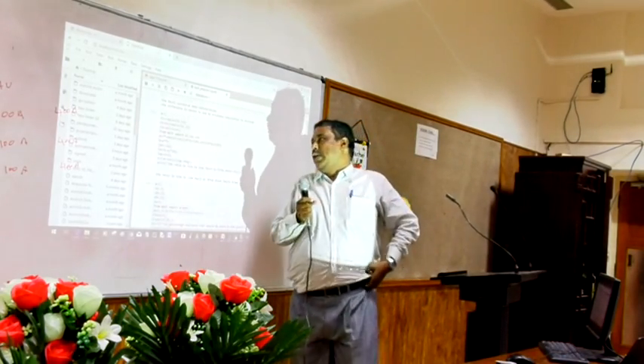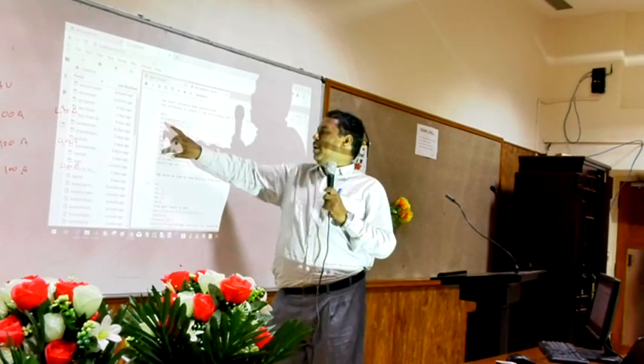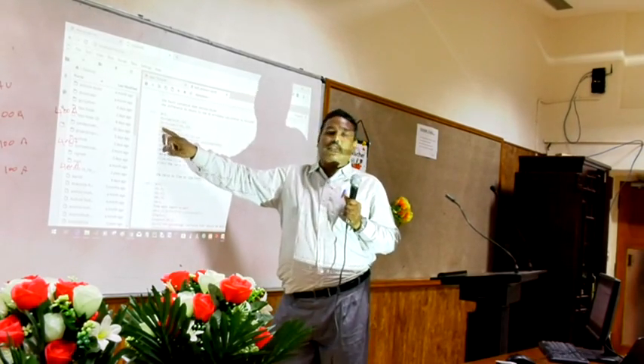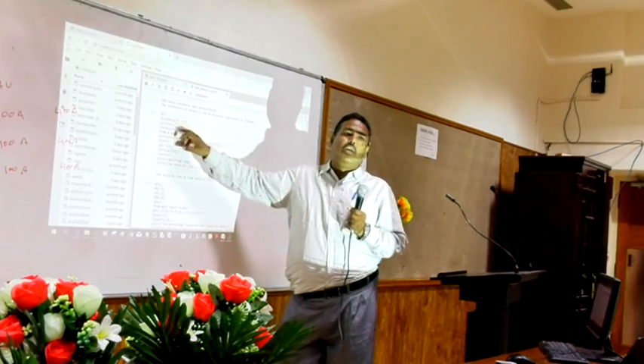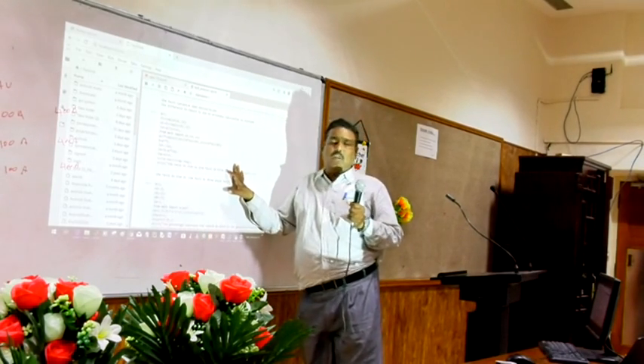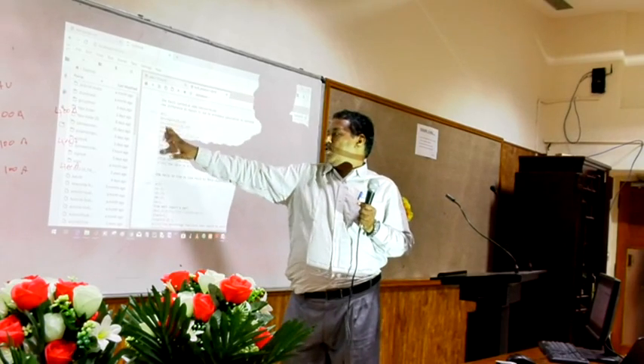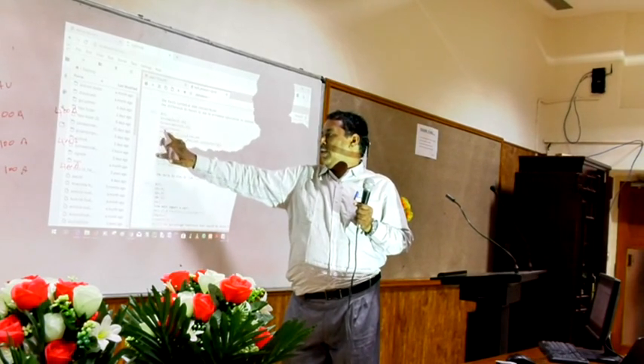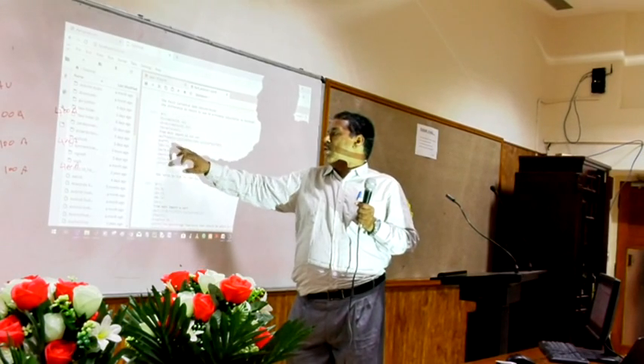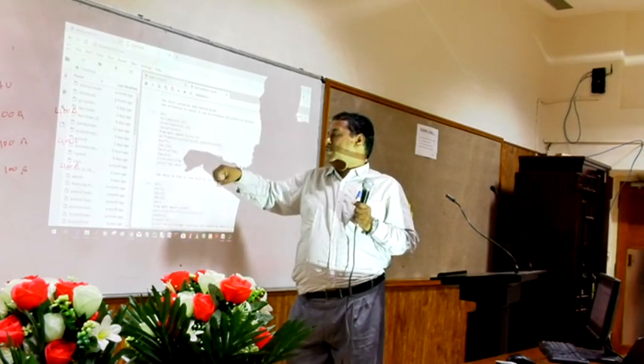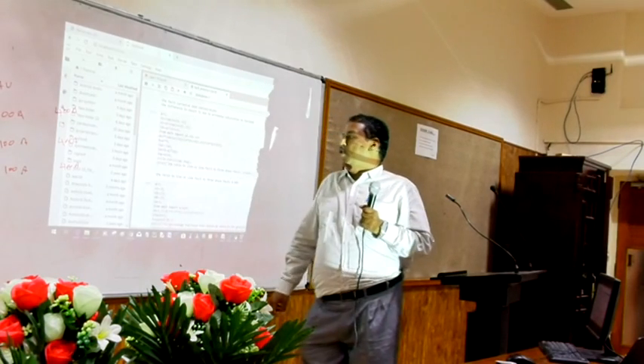Next, line to line fault. x1 equal to x2, because here you don't have x0, because there is no zero sequence in a line to line fault. So x1 and x2 are given, so the complex values are taken. IA1 equals E divided by x1 plus x2, so this is the formula. So you are including pi, cos, sin. For that you have to include the math library for running these pi, cos and sin values.